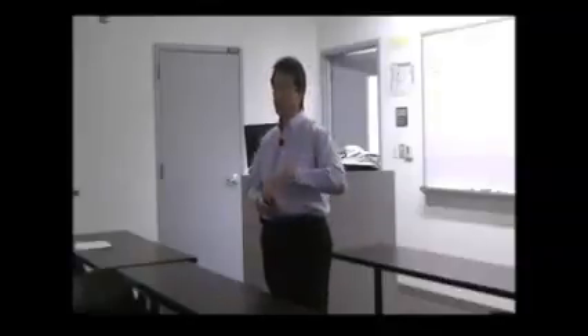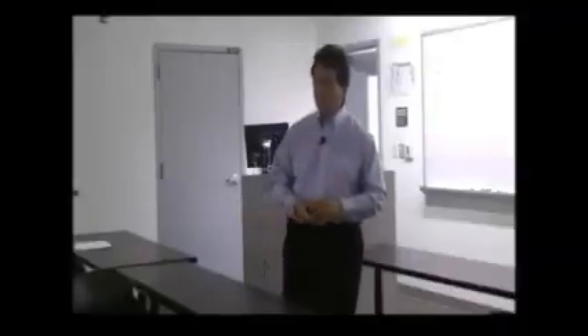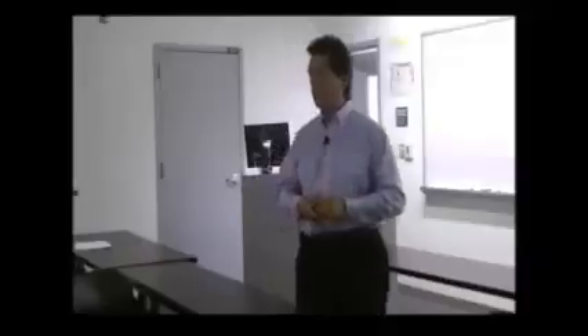We'll never go back up there again unless we do a remodel. But this particular one, with the cycles going on and off, especially in a manufacturing facility, it basically wore out the linkages. It wore out the damper blades just with the wear and tear. So now we have a PM where we go through twice a year and we inspect above the ceiling just to catch those. So these calls, as you can probably see, I still have a few, but it's not to the point that it is here.